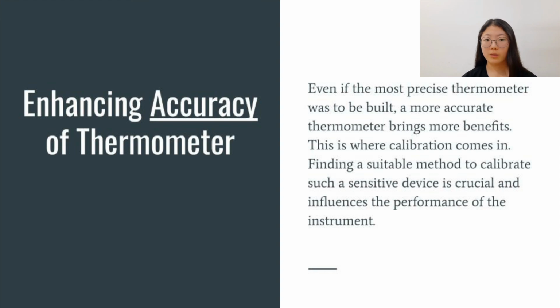Finding a suitable method to calibrate such a sensitive device is crucial and influences the performance of the instrument. Calibrating a device may be able to cancel out inaccuracy caused by zero error of instruments.